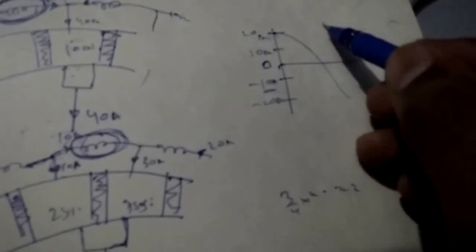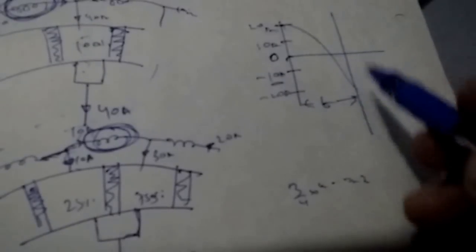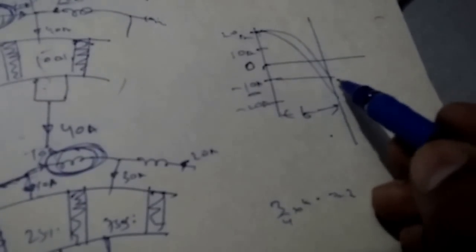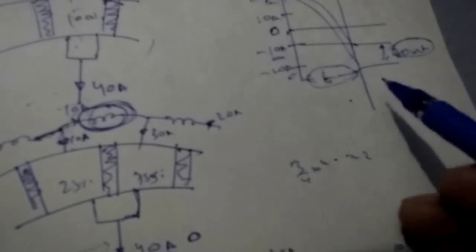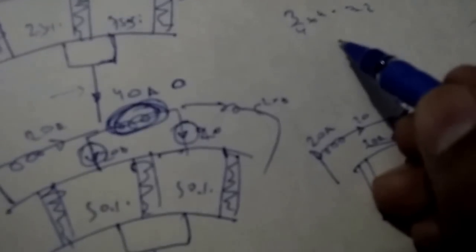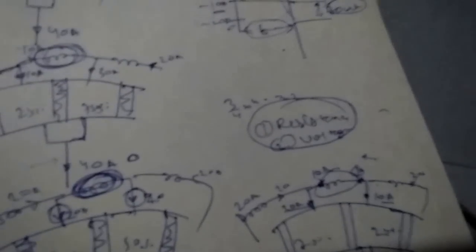This time period is called the commutation time. The faster the motor moves, the lesser the commutation time. If the current wasn't able to reverse its polarity within the commutation time, this will lead to sparking — the air around the brushes gets ionized because the current has to reach minus 20 amperes. There are two methods to avoid this spark: resistance commutation or voltage commutation. If you want videos on resistance and voltage commutation, please give feedback. Thank you.